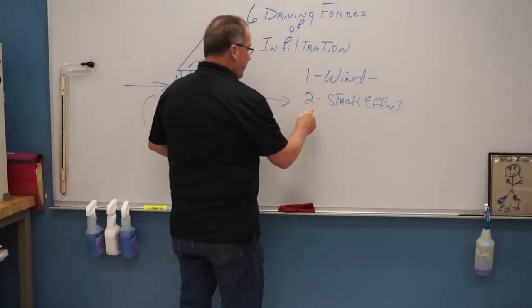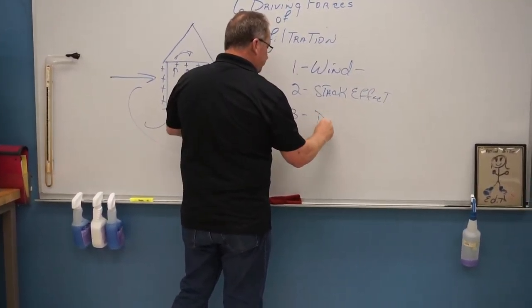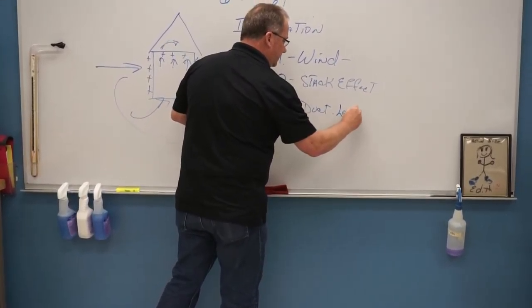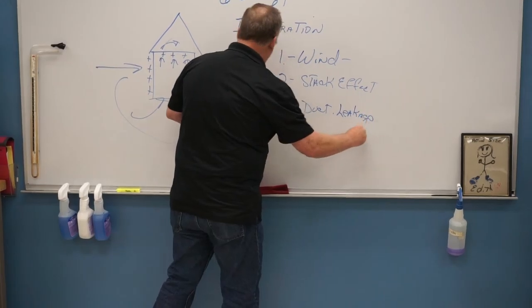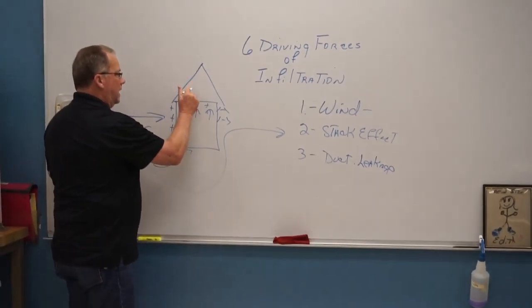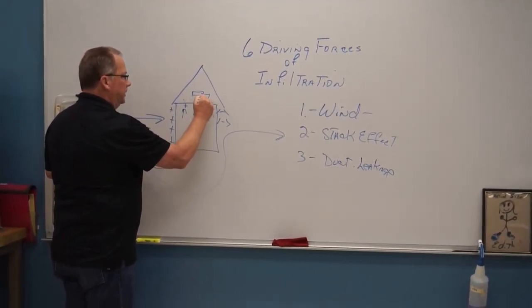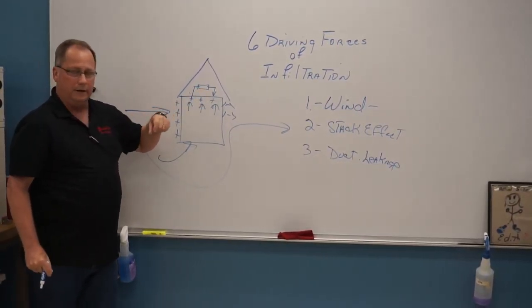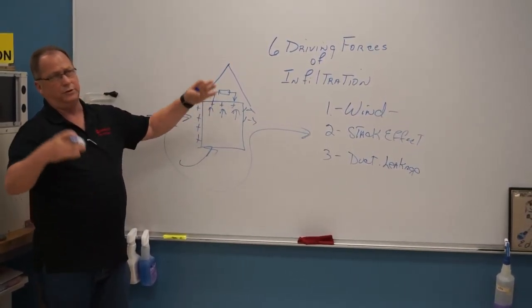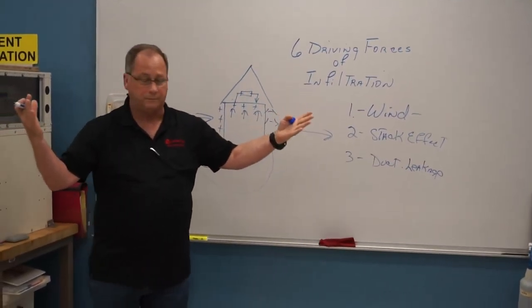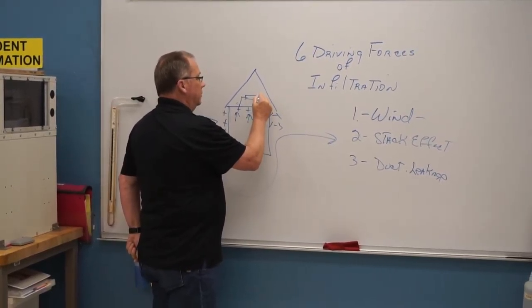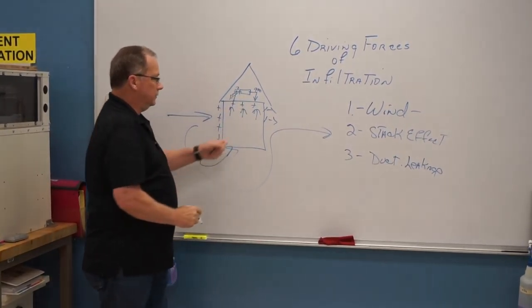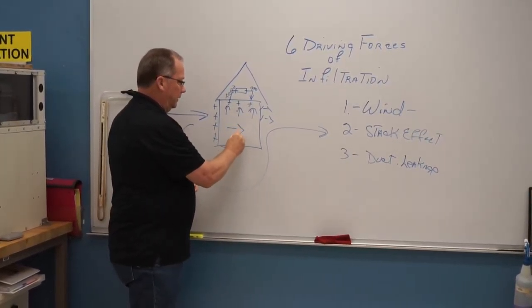So those are two naturals right there. Third thing is duct leakage that creates infiltration. So if we have duct that's up here on the top, we're supposed to be putting in the same amount of air that we're sucking out, going through our air conditioning system. And to give you an example, if our supply leaks, let's just use 1,000 CFM - 1,000 CFM of airflow - and we're only putting in 900 to the house but we're still sucking out 1,000, that means the house is going, at that point in time, into a negative.